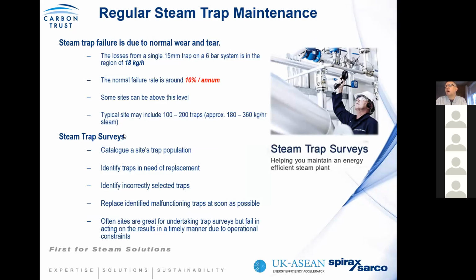So what this means is that conducting a once-off trap survey is good for the calendar year in which you have done it. But again, analysis through international best practice has identified an annual 10% year-on-year failure rate. So, for example, if you were to take a single DN15 trap on a 6-bar system, where you have a trap population of 100 to 200 traps, you could be leaking anywhere from 180 to 360 kgs an hour of steam, even conforming to best practice.